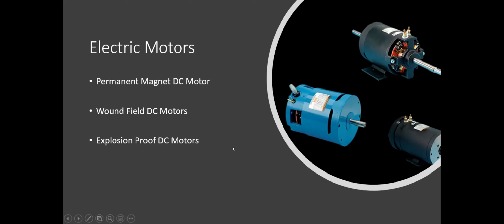Sorry. These explosion-proof motors can be either permanent magnet or wound field DC motors. And due to the fact that they're sealed, they're very robust. They're intended to contain an explosion. They're much larger and heavier than a standard motor. The newer units are moving to brushless designs that will further improve the safety of these motors. And now we'll go back to Ryan for the last portion of our report.